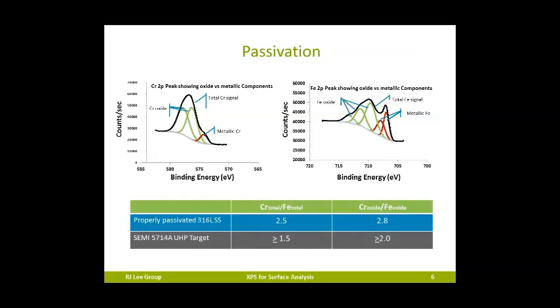The spectra in this slide can be processed by the XPS computer software to quantify these ratios of chrome, chrome oxide, iron, and iron oxides to determine whether they meet ASTM or semiconductor equipment processing specifications. In this example, the ratio of total chrome to iron and chromium oxide to iron oxide exceed the 1.5 and 2.0 ratios required for this ASTM documented process.